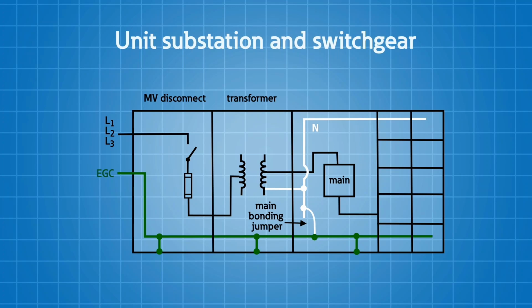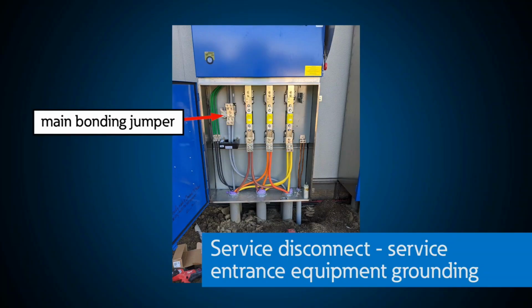Finally, for larger systems using unit substations and switchgear, here's how the grounding and bonding is done for those systems. For larger systems like the pad mounted transformer or the switchgear, if the utility owns the transformer, we would see the neutral to ground bonding jumper installed inside our switchboard or switchgear, and we would bring the grounding electrode conductor into that service equipment.